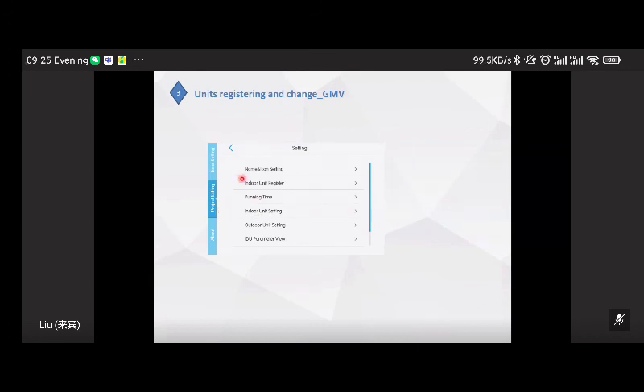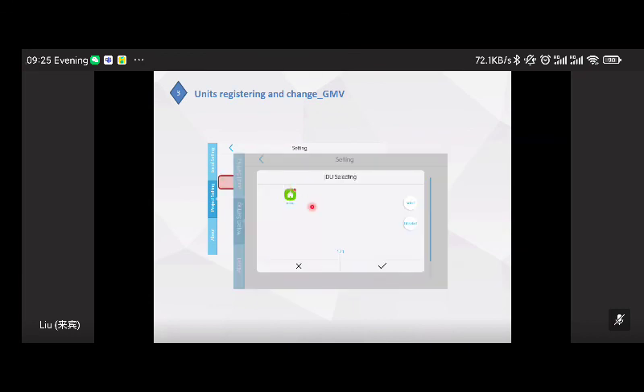Another one is a project setting, such as the Indoor units register. For example, there are many Indoor units. However, you just want to control some of them, not all of the Indoor units, right? This depends on the customer. If they have this special requirement, you can just first select the Indoor units, and then press here to confirm to register the units you select. If the units is registered, then that units will be displayed on your central controller. If not registered, then that unit will not be displayed on the central controller.